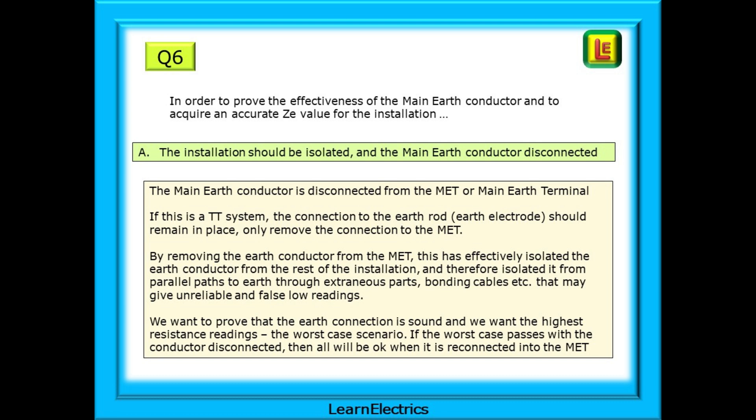By removing the earth conductor from the MET, this has effectively isolated the earth conductor from the rest of the installation and therefore isolated it from parallel paths to earth through extraneous parts, bonding cables, etc. that may give unreliable and false low readings. We want to prove that the earth conductor is actually connected to something and we want the highest resistance readings, the worst case scenario. If the worst case passes with the conductor disconnected, then all will be okay when it is reconnected into the MET.